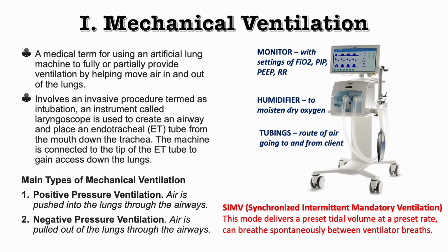One common mode used is the SIMV mode, or the Synchronized Intermittent Mandatory Ventilation mode. It delivers a preset tidal volume at a preset rate. The patient can breathe spontaneously between ventilator breaths. In short, the machine delivers the breath while also considering the patient's breath.